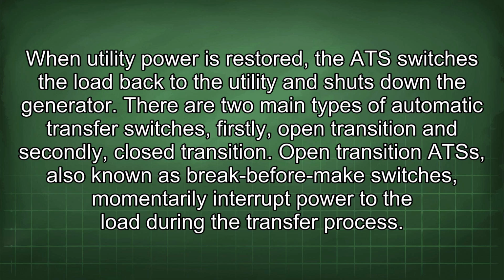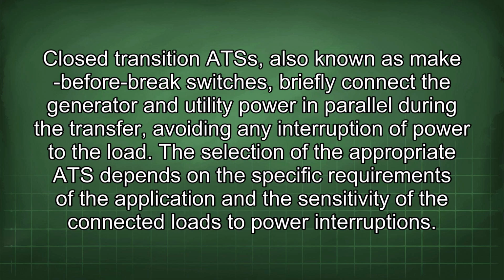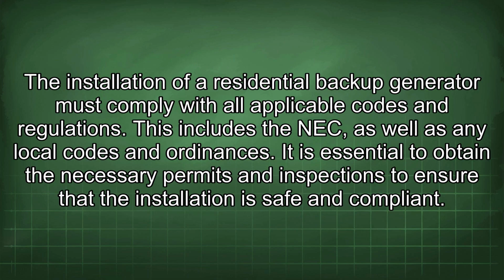There are two main types of automatic transfer switches. Firstly, open transition, and secondly, closed transition. Open transition ATS, also known as break before make switches, momentarily interrupt power to the load during the transfer process. Closed transition ATS, also known as make before break switches, briefly connect the generator and utility power in parallel during the transfer, avoiding any interruption of power to the load. The selection of the appropriate ATS depends on the specific requirements of the application and the sensitivity of the connected loads to power interruptions.